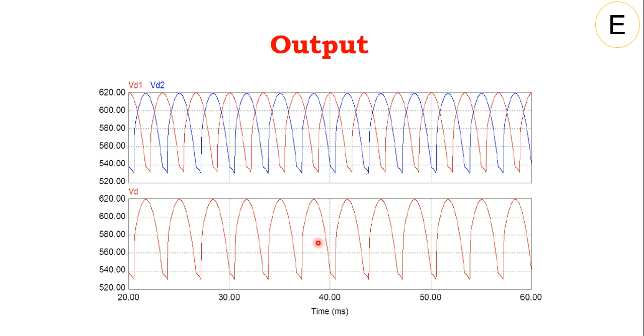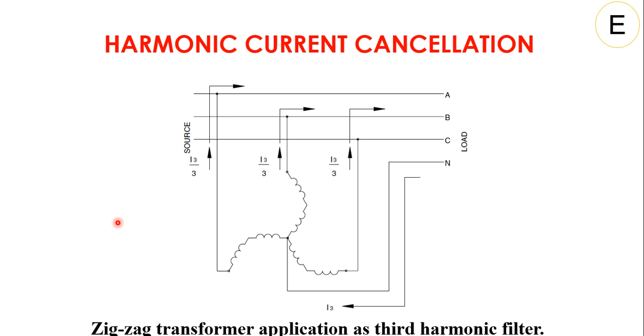We are also using harmonic current cancellation using a configuration of a zig-zag transformer to eliminate the triplen harmonics from the power system. This issue is very common for electrical power systems. So these harmonics are trapped. Similarly, cancellation of the 5th and 7th harmonics is done using a 30-degree phase shift.